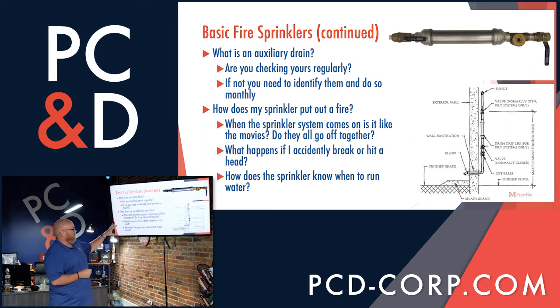Very, very critical that you keep the water drained off of your dry systems. We do not want a dry system being a wet system. When a dry system becomes a wet one, one of two things has happened. You either are not draining your low point valves, or the system has tripped and we've got water in it that way. The goal is to keep a dry system dry. So enough on that. Next slide.